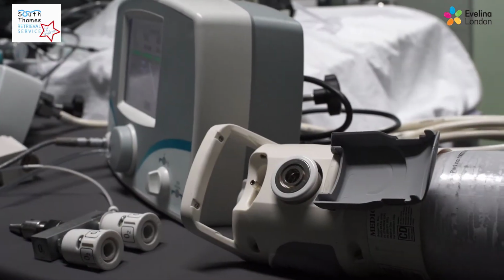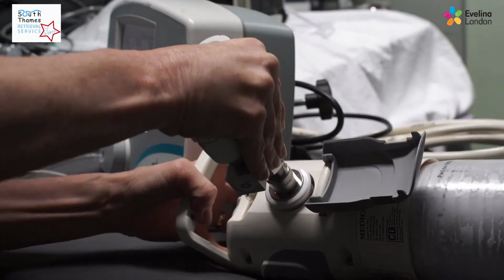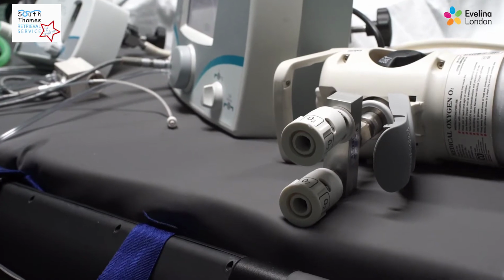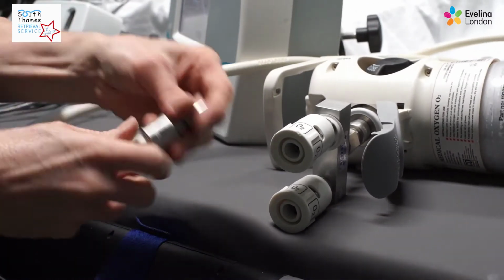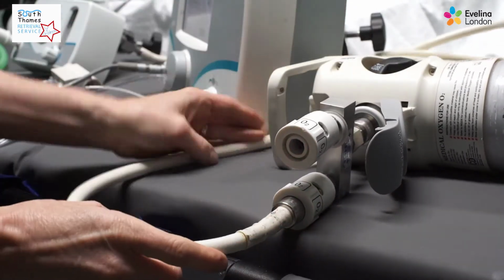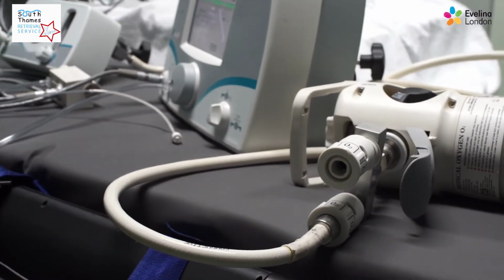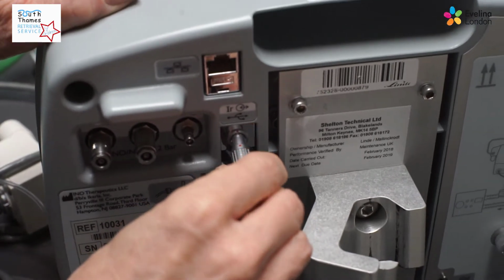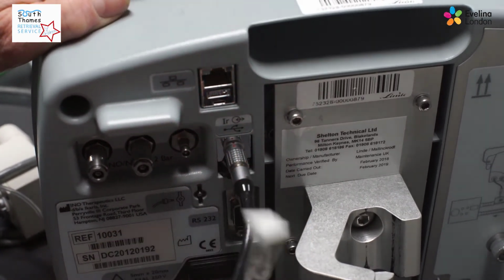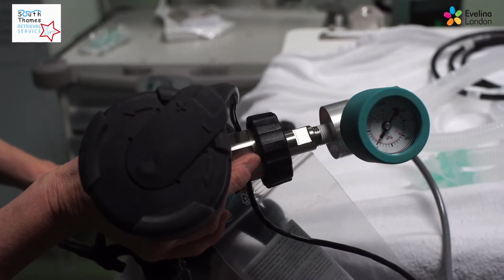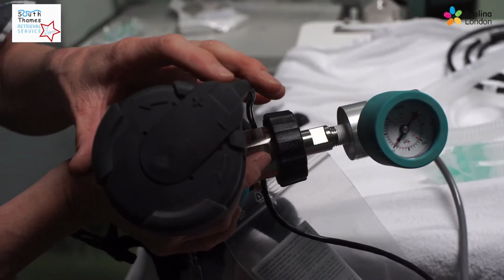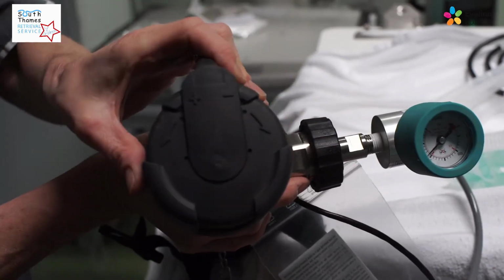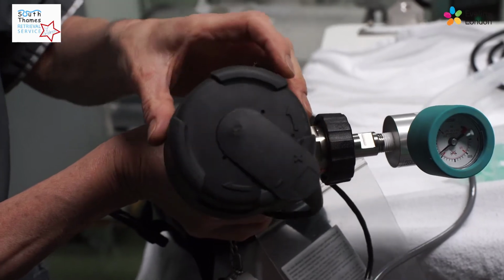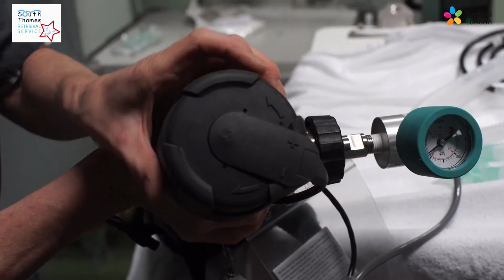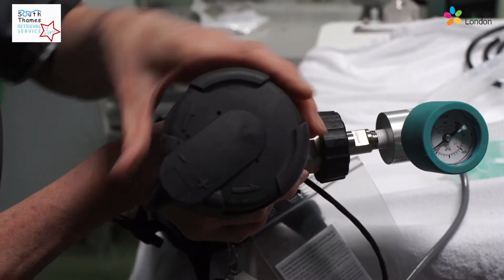So get the oxygen splitter and connect it into the oxygen cylinder. Connect the oxygen hose from the blender to the portable oxygen cylinder. Then connect the infrared, so the black lead, from the portable nitric cylinder to the monitor by lining up the two red dots and pushing it in. It is important to remember to purge the nitric cylinder before connecting to the monitor. To do this, turn the portable nitric cylinder fully on by turning the black rubber cap anti-clockwise towards the positive sign, and then turn fully off by turning the cap clockwise to the negative.